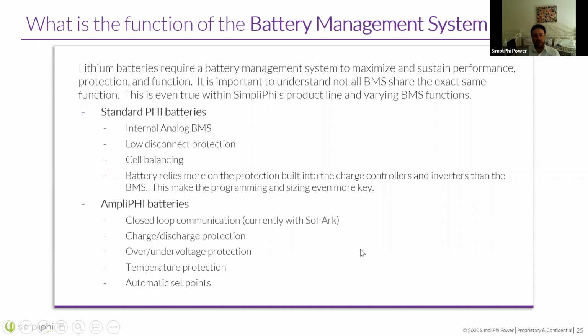When using our standard Phi batteries, the BMS is first of all an analog BMS. It's internal only, meaning no communication. As far as low disconnect protection, it does have that built in and it will disconnect. It even has some other protections built in, but I would never rely on these, as this analog BMS is really more there to keep the battery healthy over time. Cell balancing is its most critical function, I would say. We rely more on the protection built into the charge controllers and inverters than the BMS. This is why programming and sizing are so key with the standard Phi battery.